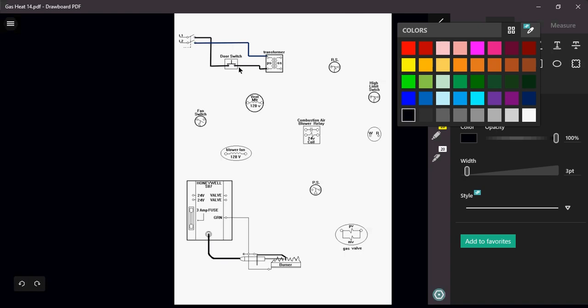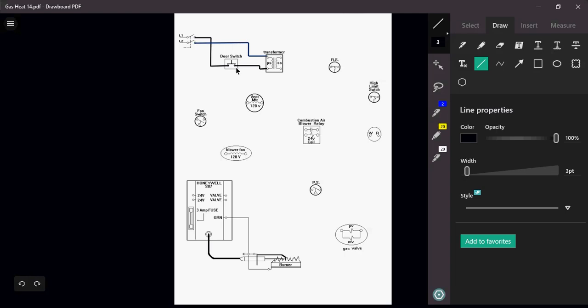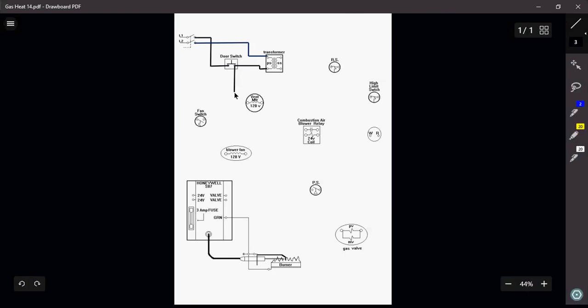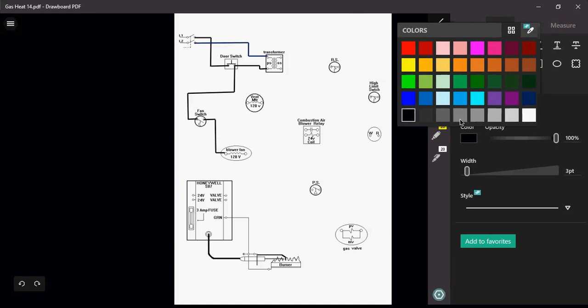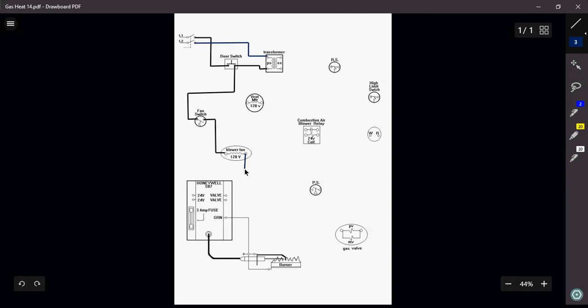So I'm going to come out of my door switch. I'm going to say right here. Okay, I'm going to go right here. I'm going to come down, and I'm going to go into my fan switch first. Because, right, that's a temperature switch, right? That's a symbol of a thermostat, right? So probably about 140, maybe 150 degrees, that thermostat's going to close, right? Once that closes, I'm now going to be able to turn on my blower. Okay, and now I'm going to send that one back to my neutral, right? Or my L2. All right, I'm just going to go this way.